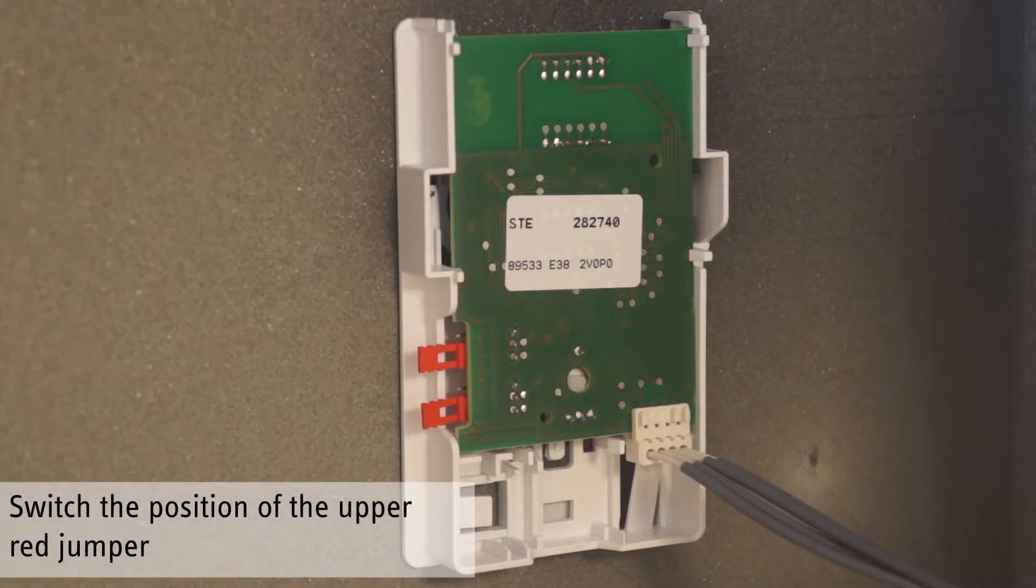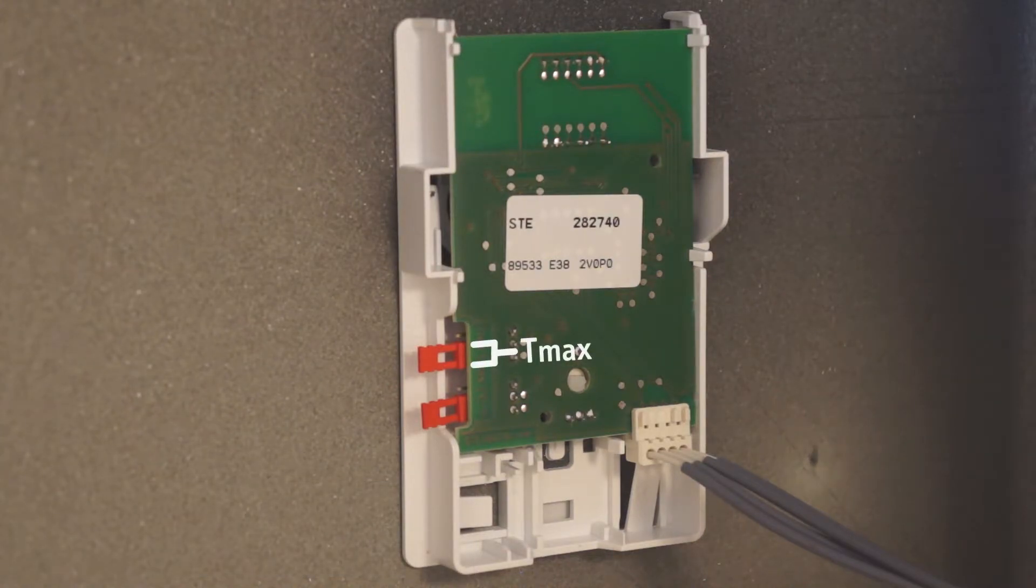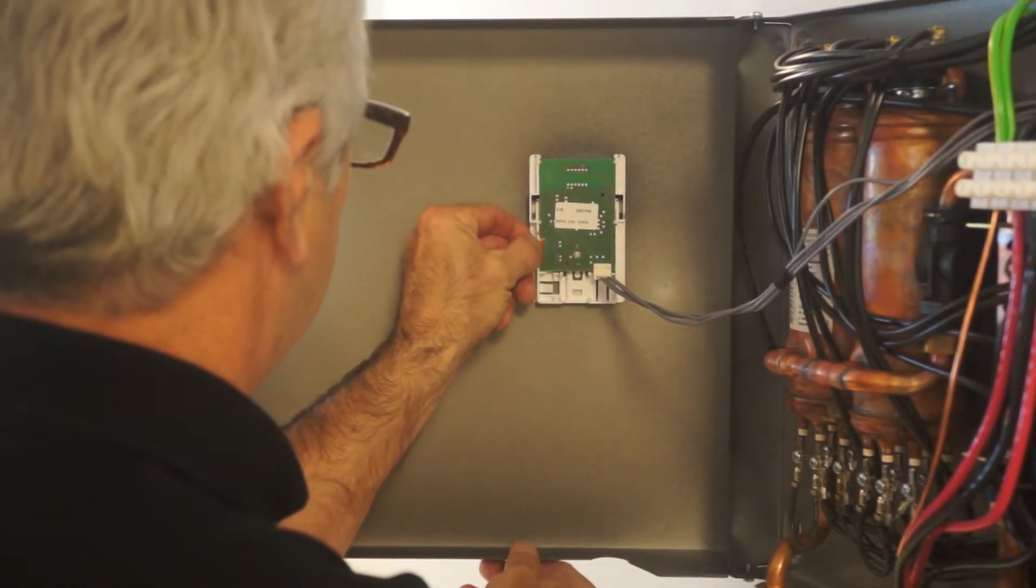The unit comes factory set to TMAX or 140 degrees Fahrenheit. To switch the unit to TRED for a maximum output of 109 degrees Fahrenheit, remove the upper red jumper from the bottom and middle contacts and reinsert it on the middle and upper contacts.